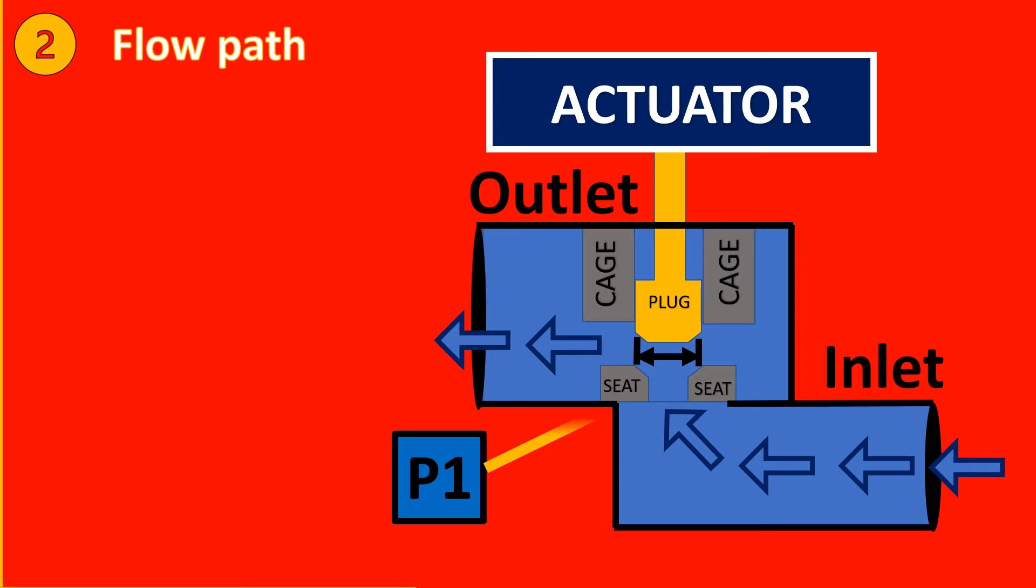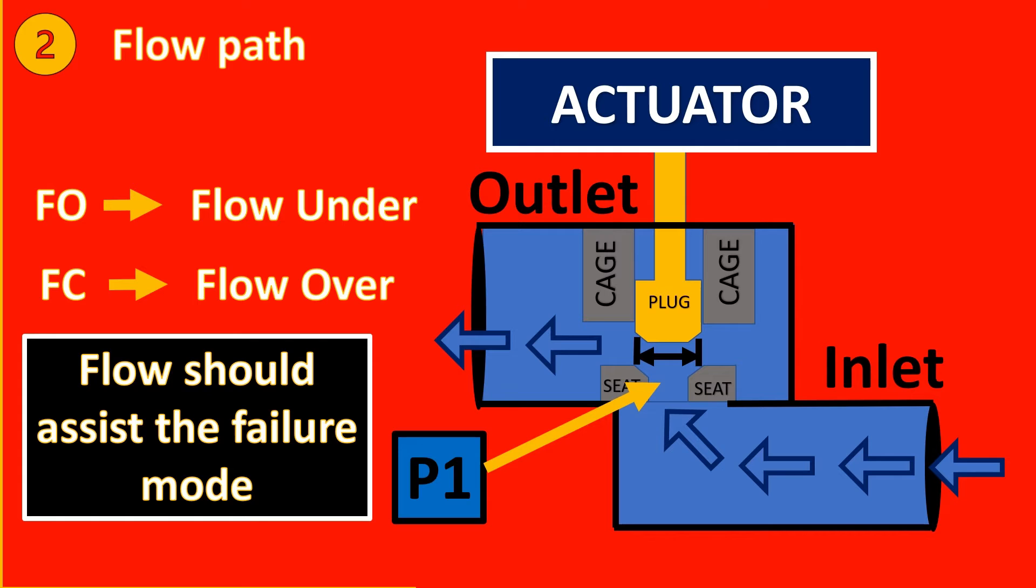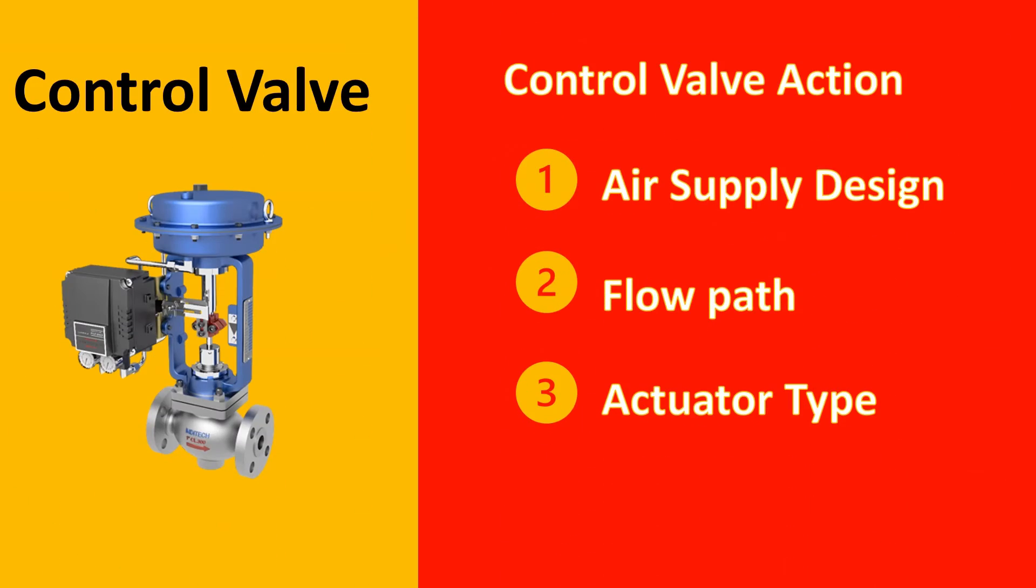Example here, the fluid flow is actually producing a pressure to put the plug in the opposite direction or in the top direction to open the valve. So for a fail open valve you should have the flow under the valve for a globe valve. And similarly fail close should be for flow over the valve in order that the flow helps to close the valve. So in a simple way you can say that as a thumb rule the flow should assist the failure mode.